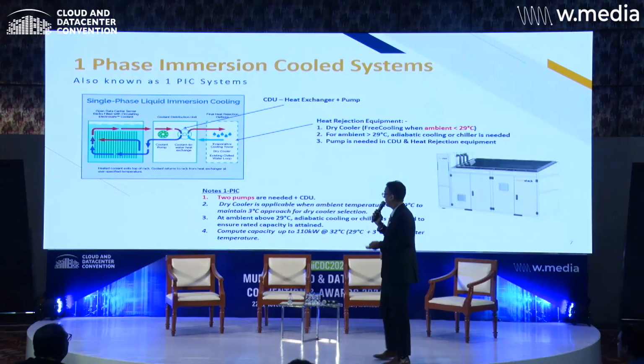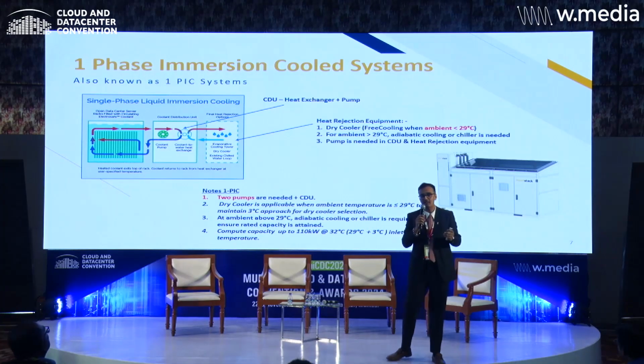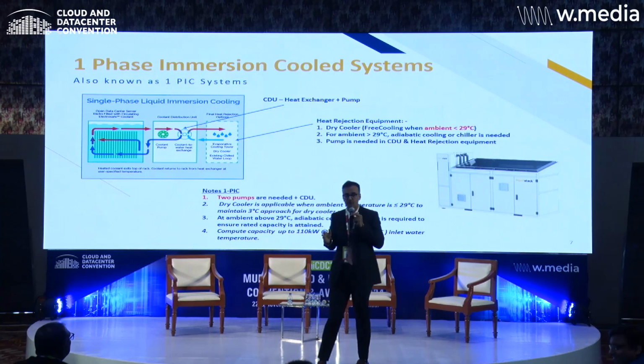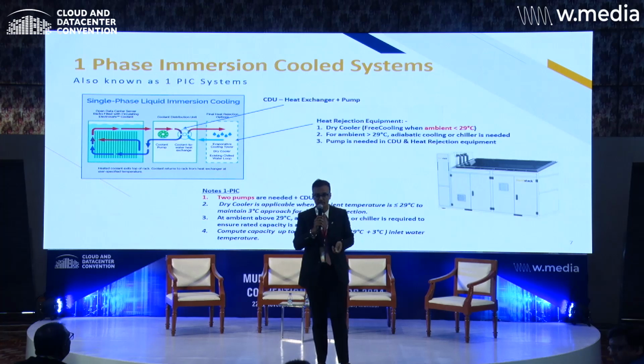It is also using oil-based liquids to cool the servers, which may or may not be conducive to your serviceability immediately, because the server has to be dried for some time when you go into one-phase immersion cooling. Over here, the compute capacity would be approximately 100 to 120 kilowatts, and the overall efficiency of the system would be between 1.2 and 1.3 PUE.